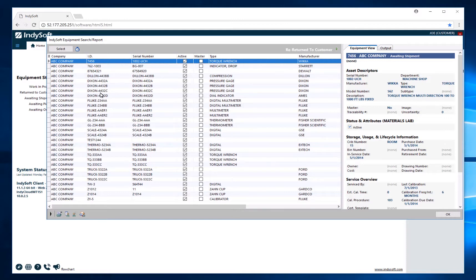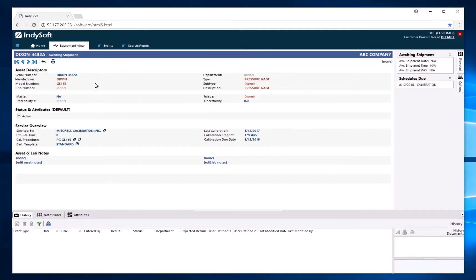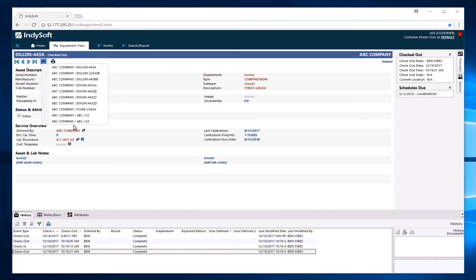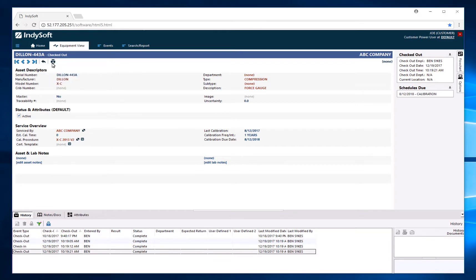If I want to go directly to an asset, I simply double click on it and it takes me to the equipment view screen. Starting at the upper left-hand corner, we have the ID, the tracking status, and the company it pertains to. We have navigational arrows, a recently viewed equipment list showing the last 10 assets you've looked at, and a printer for printing this page. We also have asset descriptors showing equipment information, active or inactive status, a service overview, last calibration, frequency and interval, and the due date.